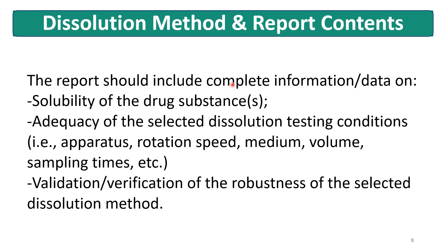The report should include complete information and data on the solubility of the drug substance; adequacy of the selected Dissolution testing conditions, including apparatus, rotation speed, medium, volume, and sampling times; and validation or verification of the robustness of the selected Dissolution Method. The solubility section will involve equilibrium solubility data, and many times the applicant also provides BCS solubility data.